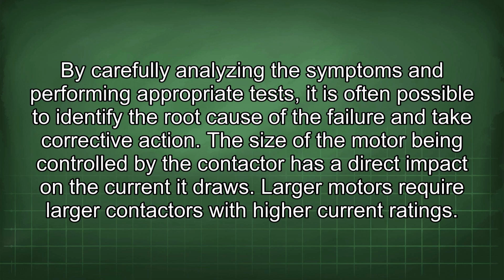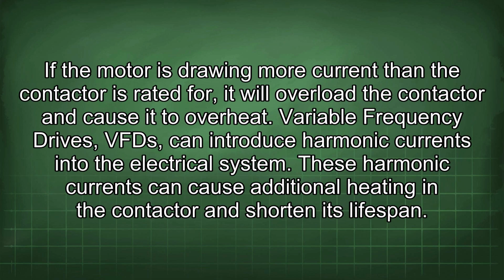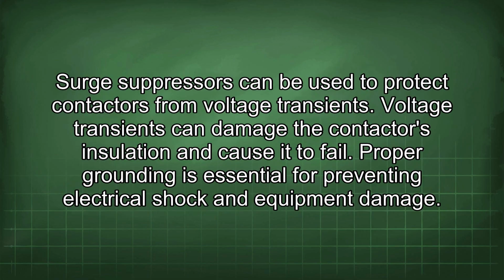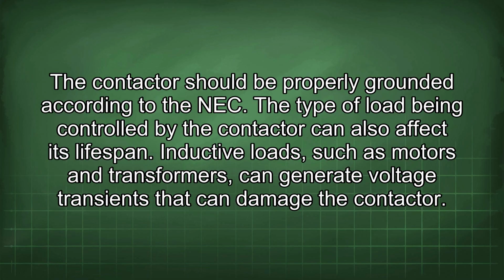The size of the motor being controlled by the contactor has a direct impact on the current it draws. Larger motors require larger contactors with higher current ratings. If the motor is drawing more current than the contactor is rated for, it will overload the contactor and cause it to overheat. Variable frequency drives, VFDs, can introduce harmonic currents into the electrical system. These harmonic currents can cause additional heating in the contactor and shorten its lifespan. Surge suppressors can be used to protect contactors from voltage transients. Voltage transients can damage the contactor's insulation and cause it to fail. Proper grounding is essential for preventing electrical shock and equipment damage. The contactor should be properly grounded according to the NEC.